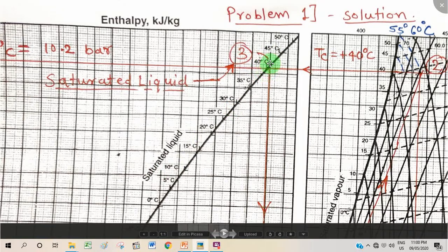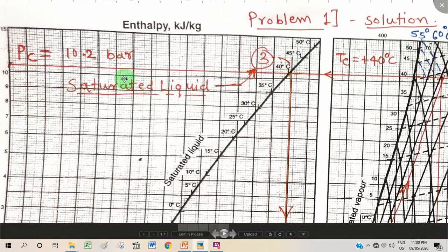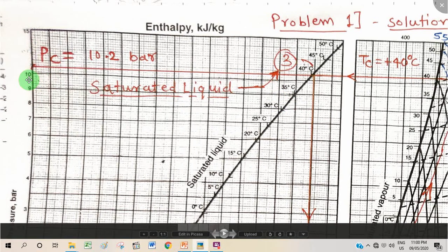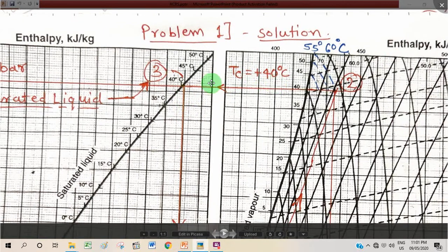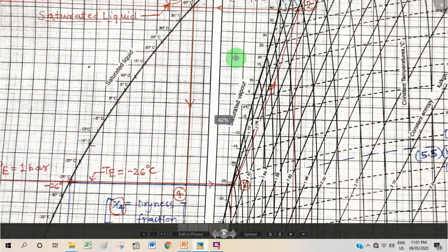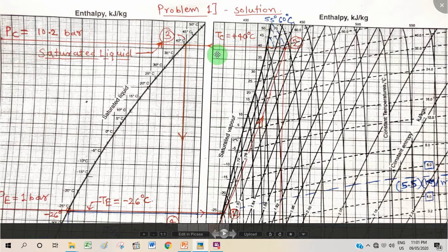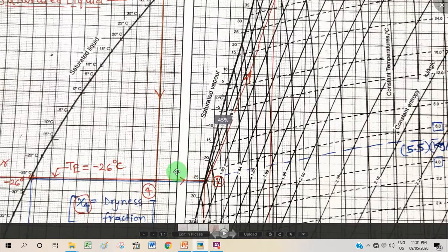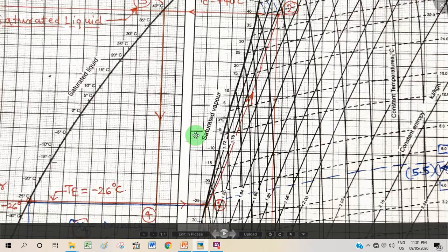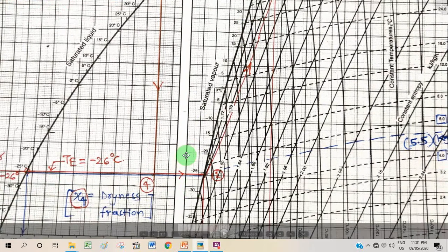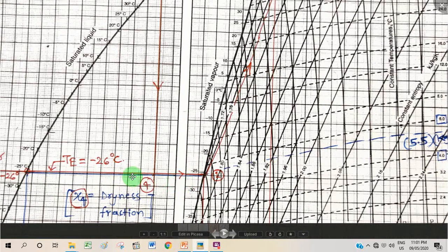Next, we locate the condensing temperature of 40 degrees Celsius on the saturated liquid curve and pass a horizontal constant-pressure line through it. This line crosses the pressure axis somewhere between 10 and 15 bar. By interpolation and judgment, I obtain approximately 10.2 bar as the condensing pressure. So the VCRS cycle works between the condensing pressure of 10.2 bar and the evaporating pressure of 1 bar.